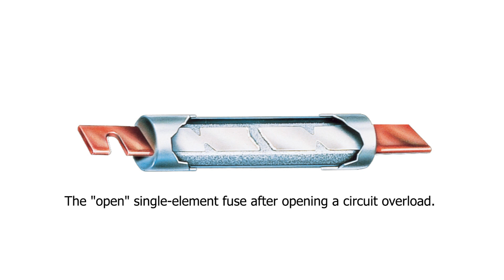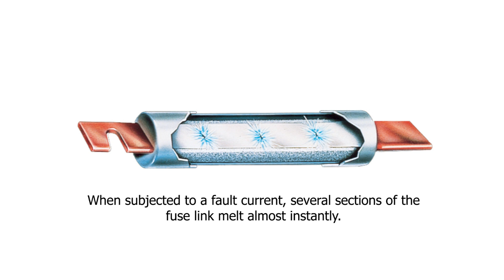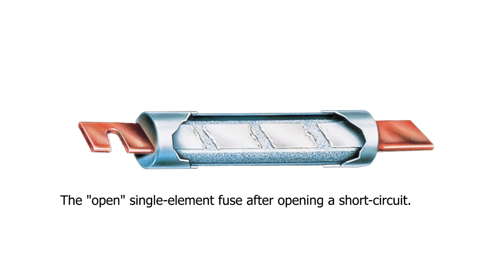Subjected to fault currents of 30,000 amps or higher, the fuse's current limiting response is extremely fast, as its restricted link sections will simultaneously melt. The multiple arcs' high total resistance, together with the arc-quenching filler material, results in rapid arc suppression, and clearing the fault typically takes less than a quarter cycle or 4 milliseconds.